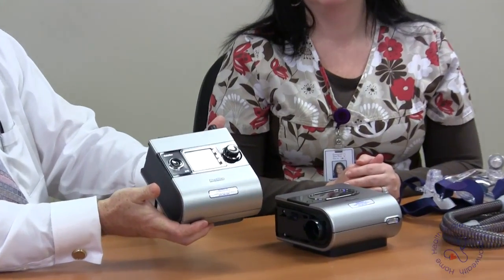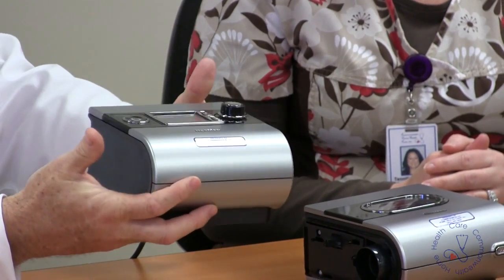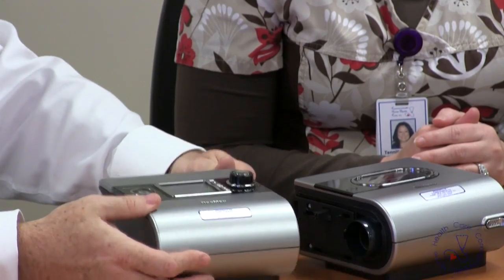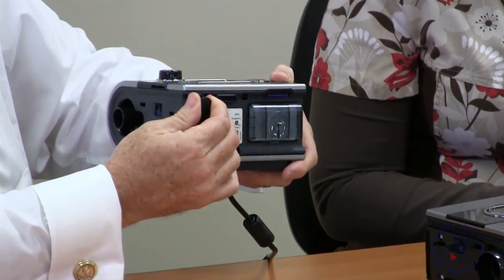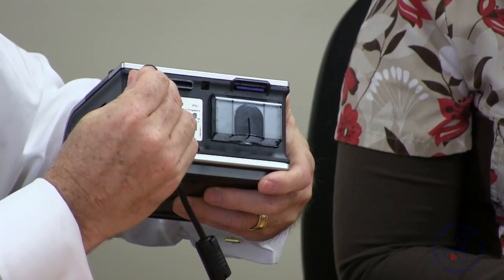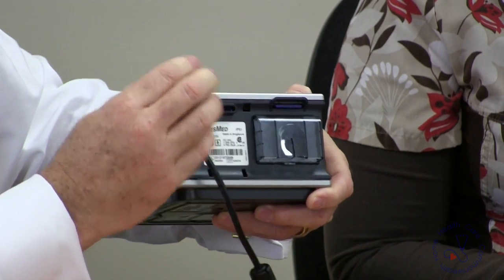This device comes in two pieces. This would be the CPAP side, and this side is what you would see all the time when a patient uses it. They have to have this side. On the back of this device, there's a plug-in. This is where the power plugs into the back of the machine. Sometimes that can come loose, not fall out, but be loose. And you would think, well, my machine's not working, I don't understand, and it's because it's not getting power. Remember, when the machine is plugged in and it's plugged into a wall, you're going to have a screen that lights up. And if that screen is not lit up, we have a power problem. Automatically, we know something's not plugged in right, or for some reason we're not getting power.